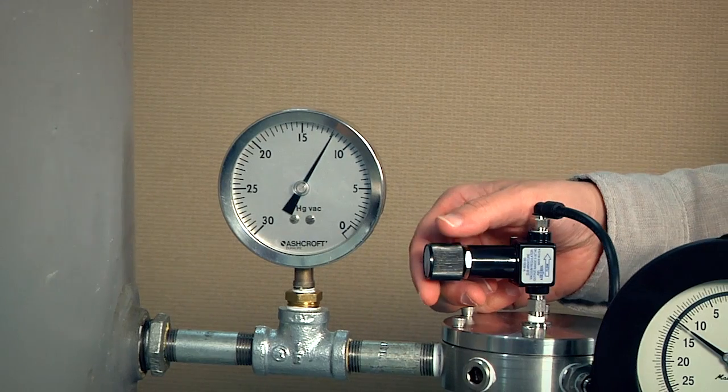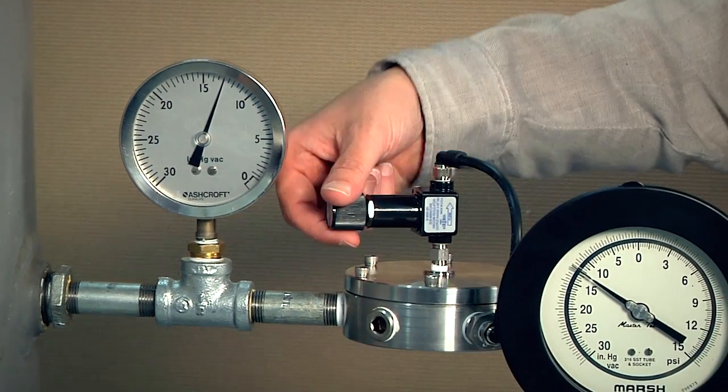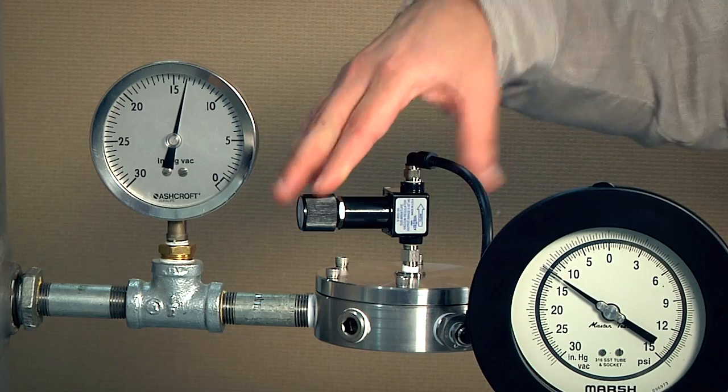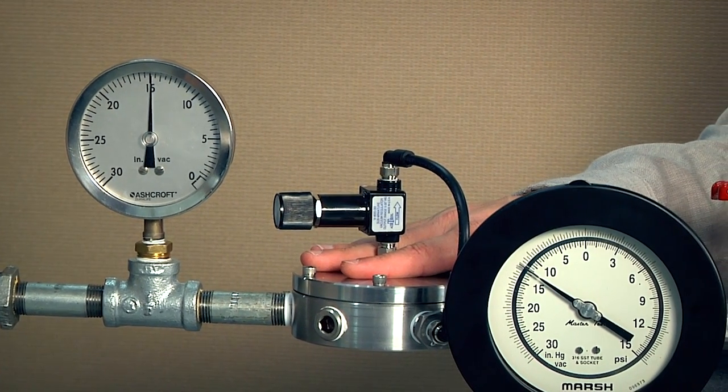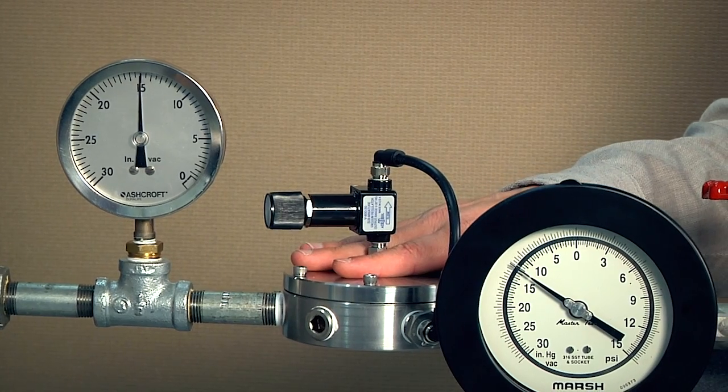I'm going to be able to set the vacuum pressure in the system by turning this hand knob. This hand knob adjusts the pilot to the Equilibar high flow vacuum regulator and determines the vacuum set point.